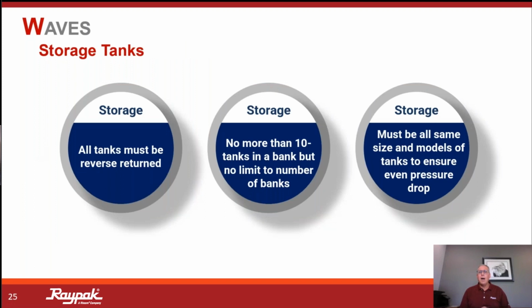Storage tanks. We don't see this often, but there are some rules to follow with our use of storage tanks. And this is right out of the manual. This is not something I'm pulling out of thin air, but we are familiar and accustomed to doing reverse return. So the first in, last out principle. But this product wants to see no more than 10 tanks in a bank of storage tanks. That way, they're all similarly sized.